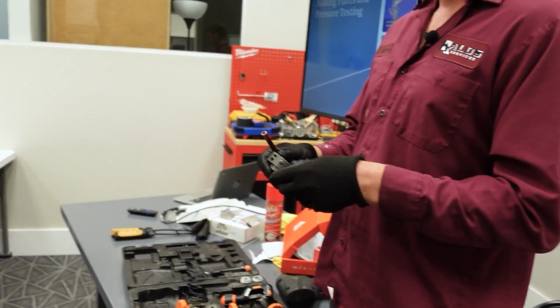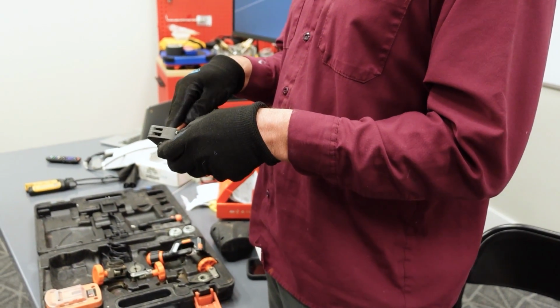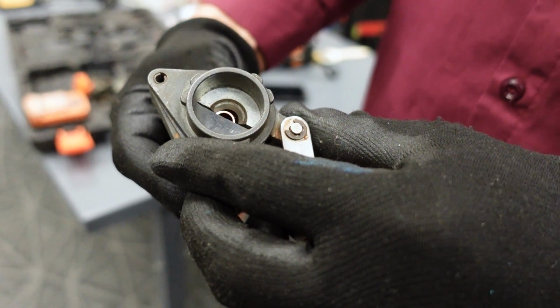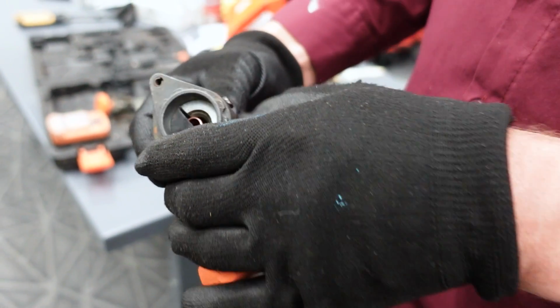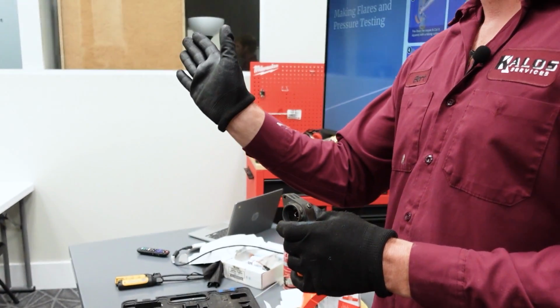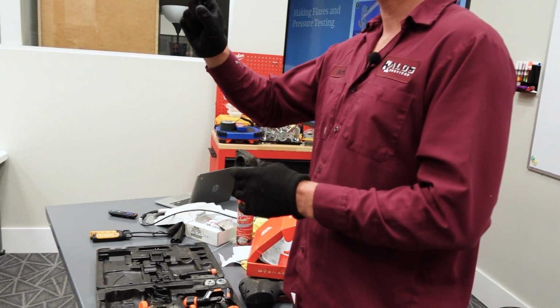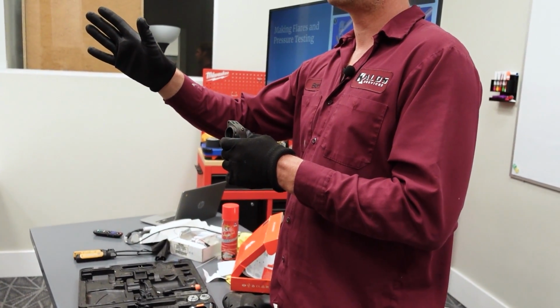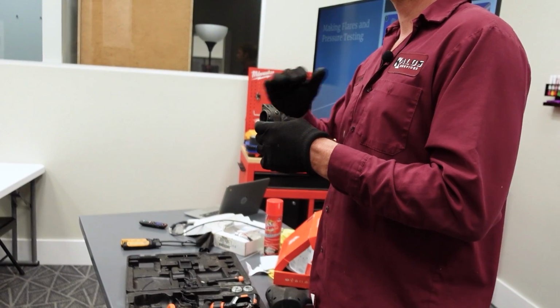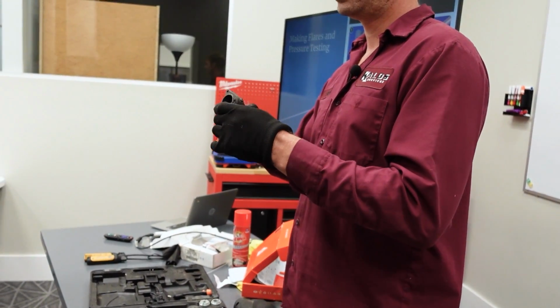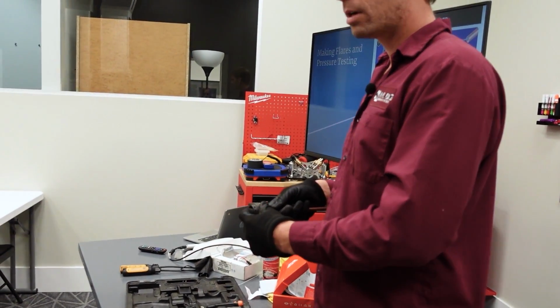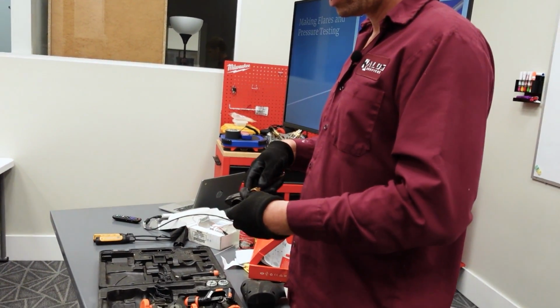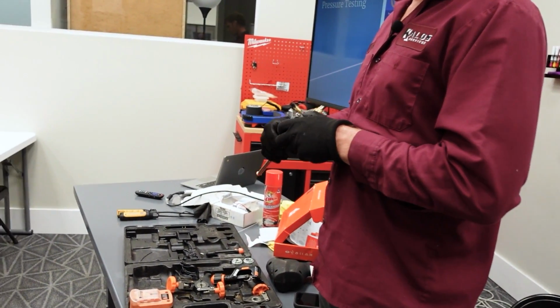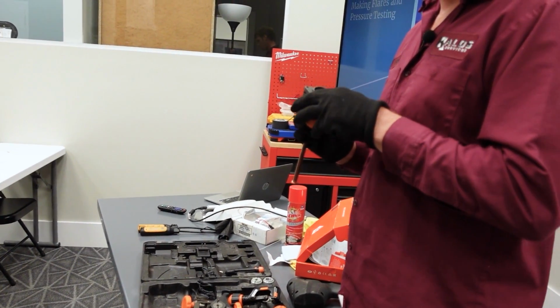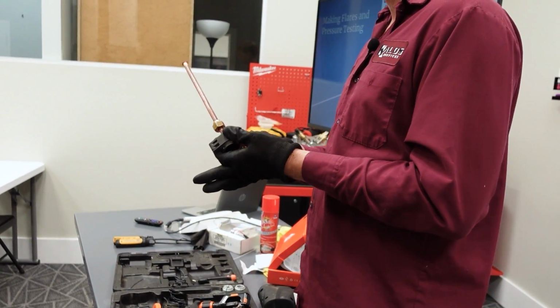With the NAVAC swedge kit, it's super easy. You slide it in, and it has a little guard right here that stops the copper as deep as it needs to go. The reason is you want your flare angle to match the nipple on the other side, not sticking too far into the threads, not too short so there isn't enough surface pushing together. This has a guard on it, which is another reason why these are so great, so you push it against that guard and you know you're at the right depth.